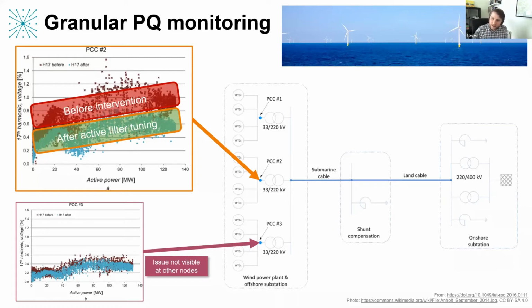So this granularity of monitoring at multiple locations is actually very important. Otherwise, you might miss something. In this particular case, at the onshore connection, at the grid connection point, it reduced the impact of that harmonic in terms of grid code requirements, so that was brought down into an acceptable region. It also meant that in general the wind farm was operating more efficiently, with less losses and power dissipation due to the power from that harmonic. And it also meant that the stability was improved. The control stability of the wind farm benefited from getting rid of that resonance.